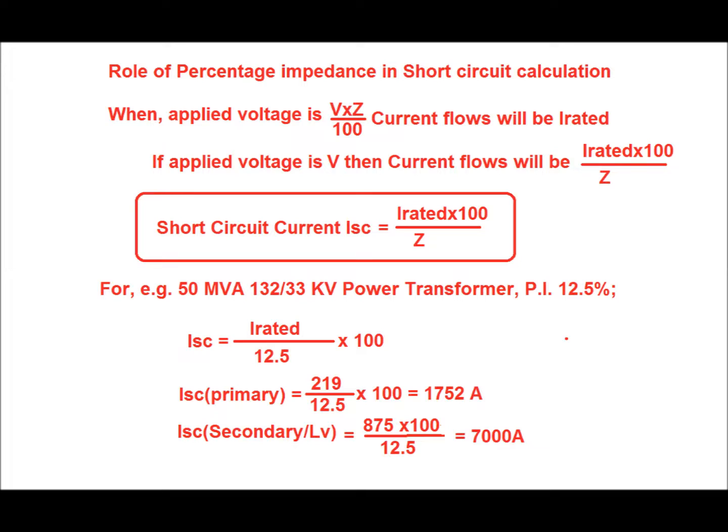The role of percentage impedance in short circuit calculation: when applied voltage is V × Z / 100, current flow will be I rated. If applied voltage is V, then current flow will be I rated × 100 / Z. Therefore, short circuit current ISC = I rated × 100 / Z. For a 50 MVA, 132/33 kV power transformer with percentage impedance of 12.5%, ISC on the primary side = 219 / 12.5 × 100 = 1752 amperes. For the secondary or LV side, short circuit current = 875 × 100 / 12.5 = 7000 amperes.